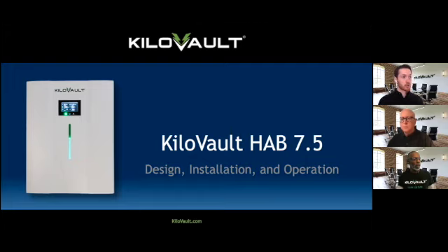And then one other quick one from Joe. A good question. Does partial charge and discharge, like a real off-grid scenario, affect battery life? One of the benefits of lithium iron phosphate is that they're really not concerned about getting a nice full charge and discharge cycle as you would be with a lead acid battery. There's no sulfation, which is really the reason to do not only equalizing, but also regular charging and discharging. Lithium iron phosphate batteries actually like to sit in a partial state of charge. If they're sitting at 80, 90% state of charge, that's where they're happy. So no, there is no risk at all to not fully recharging the batteries, aside from not taking advantage of the full capacity. And there's no risk of letting them sit in a partial state of charge.